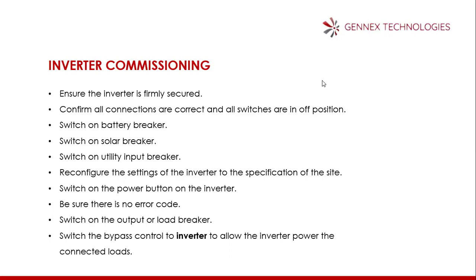Even if the inverter is showing a warning code for frequency loss, that means input is lost, which means your utility is not available. That's not a problem. But if your utility is available at that time, it won't show any warning. Everything will just work perfectly. So be sure there's no error code. Switch on the output or load breaker. Switch on the bypass control to inverter to allow the inverter power the connected load.